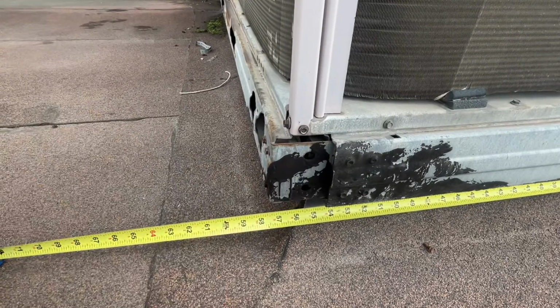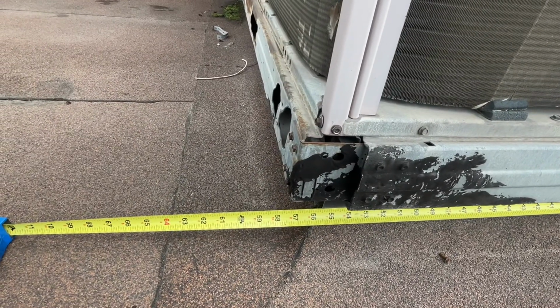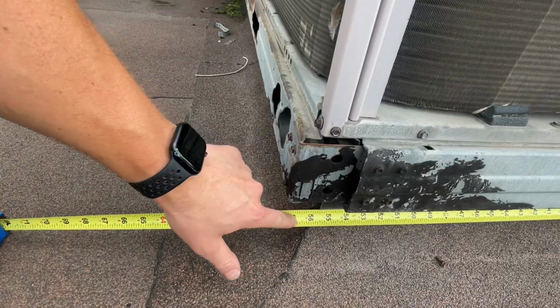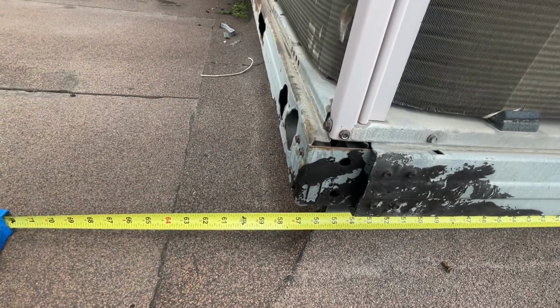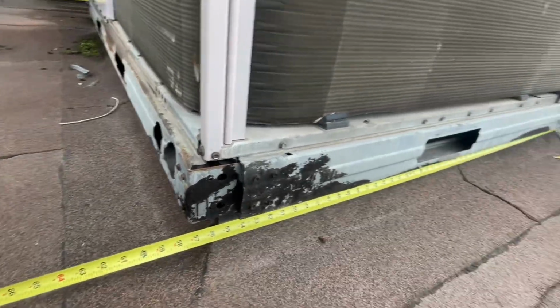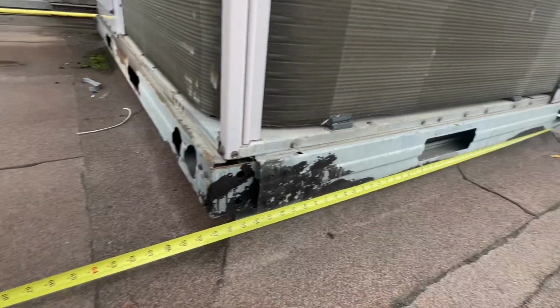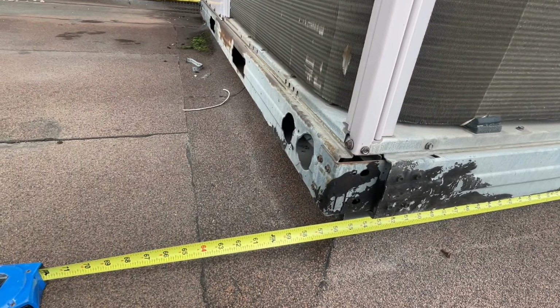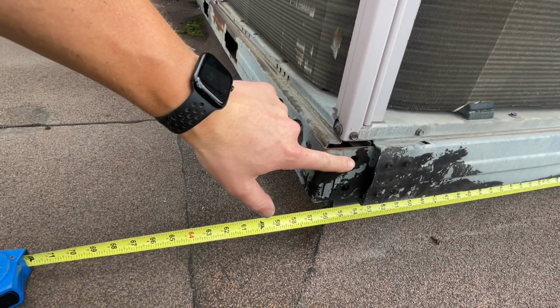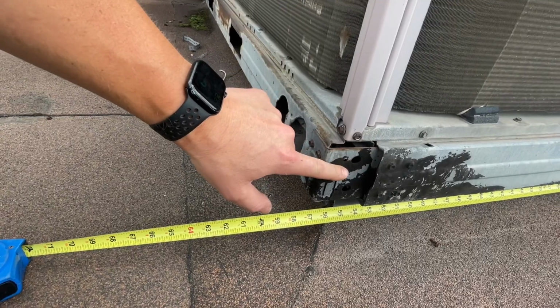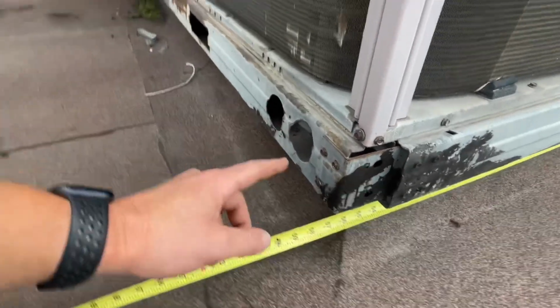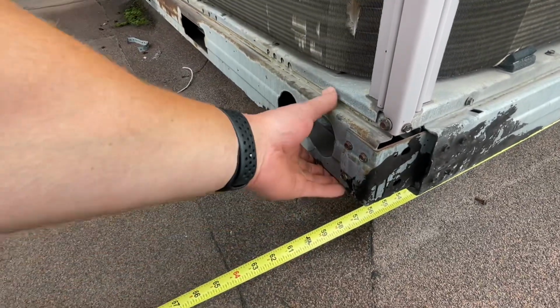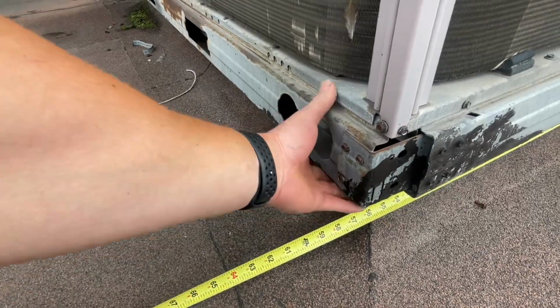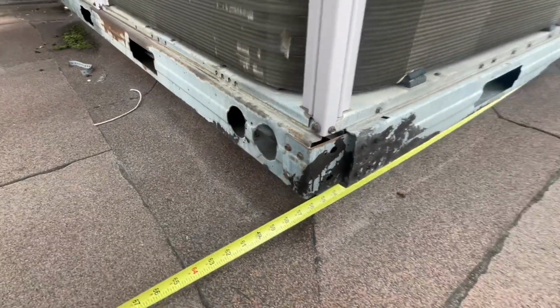So what I like to do sometimes is I will upsize my measurement by about 1 inch, so 1/2 inch on each side, just to make sure that when this new rooftop comes, we're not gonna have any issues with this not fitting. I've been on jobs before where the rooftop was ever so slightly too small. You have to start undoing these hoisting points to open up this bracket, and it's just an absolute nightmare.